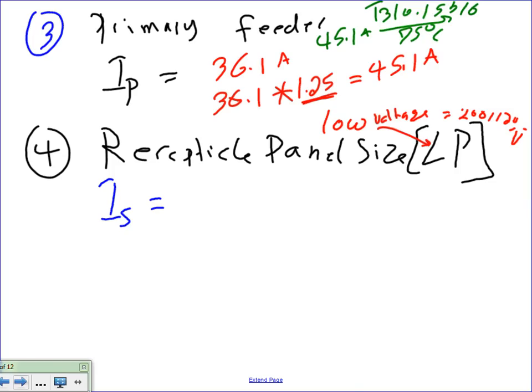What's the conductor size? Anybody? Number 8. Still number 8? Good grief, I thought it goes up to 50 amp. Okay, number 8. Now how many conductors though? 3. Thank you. I need 3 conductors. Number 8 AWG THHN. So 3 conductors, number 8 AWG THHN. Now assuming it's continuous load and we size that baby. Okay. Any questions about this?